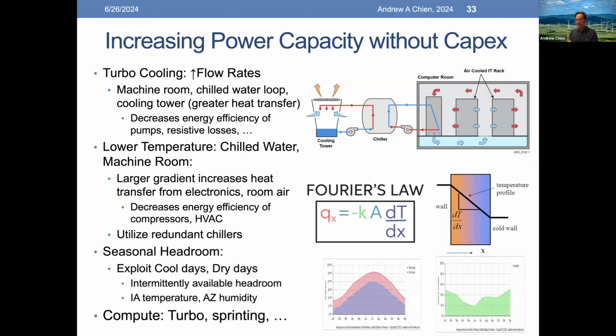And then finally, one thing that's often ignored but came to the fore when several regions had record heat: it turns out there's seasonal headroom also in almost all locations. What you can see at the right here is that the temperature in a region varies over time, and the humidity in a region varies over time. These are monthly charts. Pretty rare you see a monthly variation chart. But what that means is that, in Iowa or in Arizona, you can run at different capacities at different times of the year because intrinsically your cooling problem is different because of the external environments.